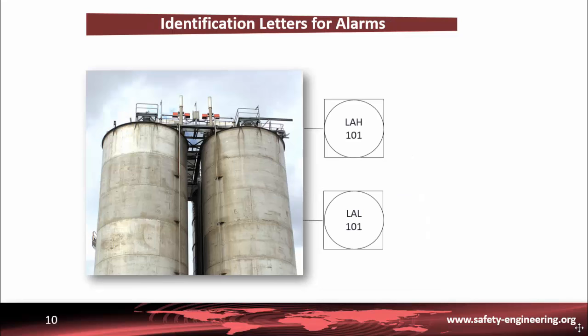In order to warn operators of potential problems, alarms are placed in the control room. These could be high-measure alarms or low-measure alarms. The tagging identification letters for alarms are straightforward. The first letter is the measured variable — here, level. The letter A placed in the second position indicates that the symbol is associated with an alarm. So this alarm is applied to the level.